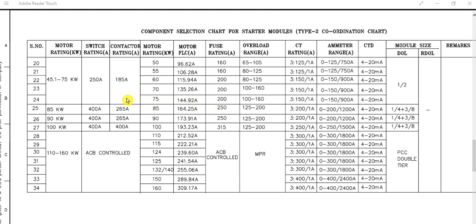And on the left hand side you can see this is the switch rating, 250 ampere, and contactor rating, 185 ampere. So first of all we need to choose the switch rating 250 ampere. Next is the contactor rating 185 ampere. Next is the fuse rating, which is 200 ampere for the 75 kilowatt motor. Now from the protection point of view, the overload protection setting needs to be set between 100 to 160 ampere, within this range.